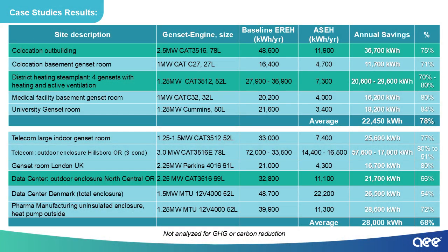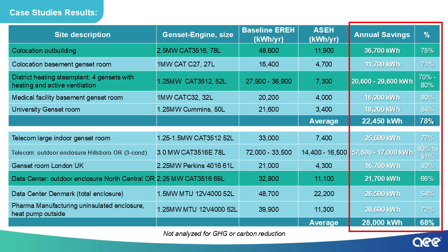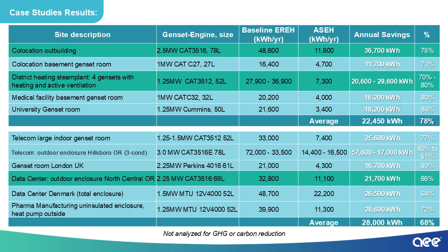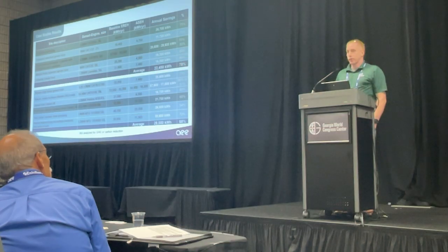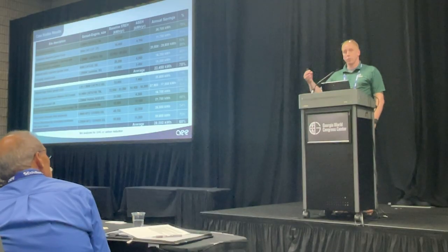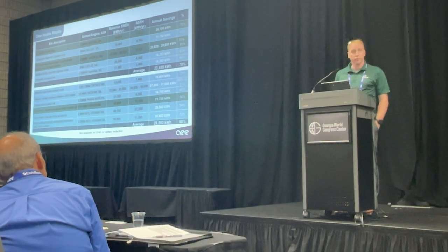So if we summarize all 11 case studies, and again, the other ones are available at the end of this appendix if you get the slides for this, we had a range of savings from a little less than 17,000, 16,000 excuse me, to upwards of 57,000 kilowatt hours per year saved per genset. Obviously, as the number of gensets increases for a location, this multiplies the savings for that facility significantly.